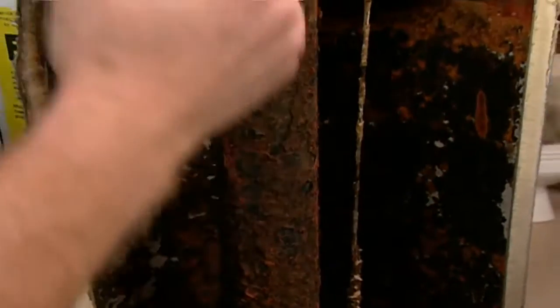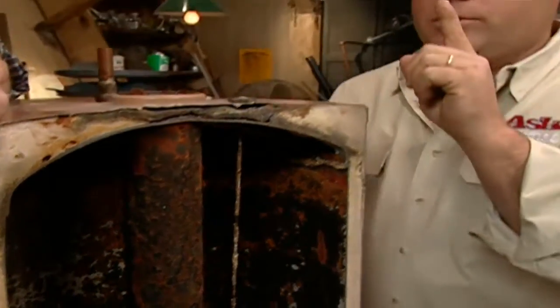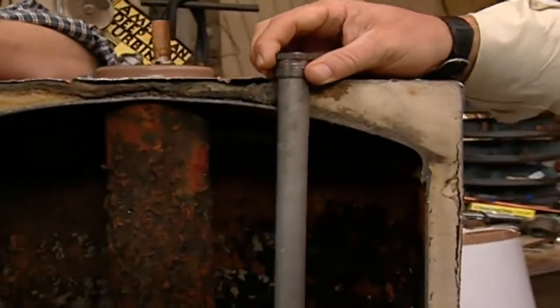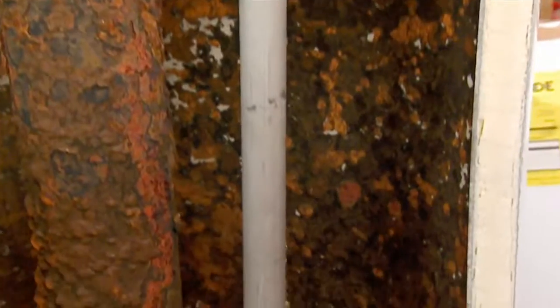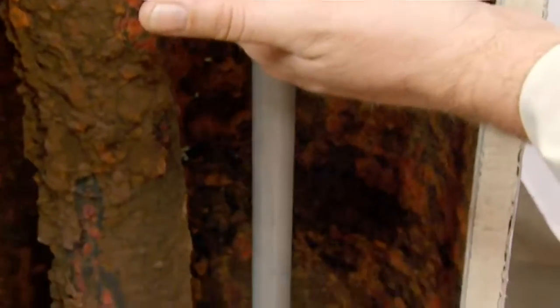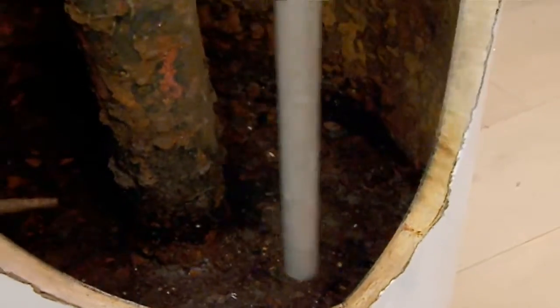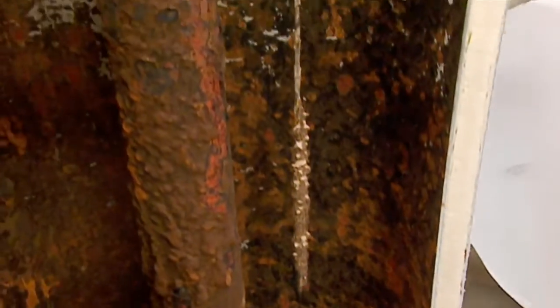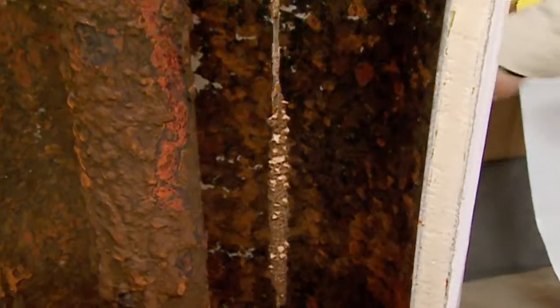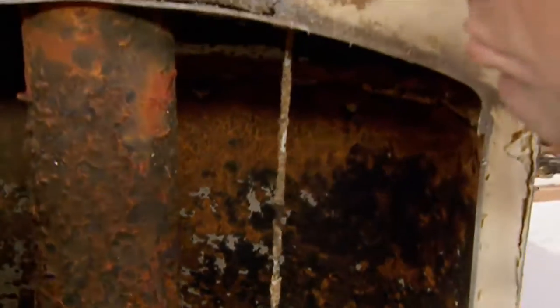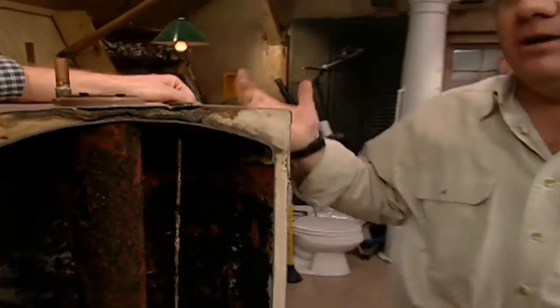Now, water, in the presence of oxygen, will always try to eat any metal. So inside of any water heater will be a rod like this. This is a sacrificial anode rod that sits down into the water. Sacrificial? Why sacrificial? It's made out of magnesium. It's a less noble metal than the tank, so this is what gets eaten. Look what ours looks like. It's completely gone, completely eaten away. Absolutely. Now, once that anode rod is gone, the water now has a veritable buffet. It can eat the entire tank, and that's what happened.